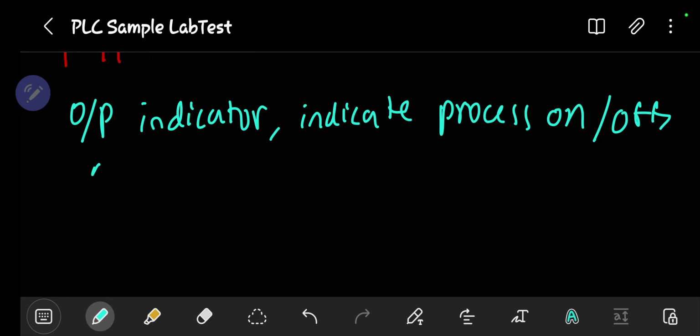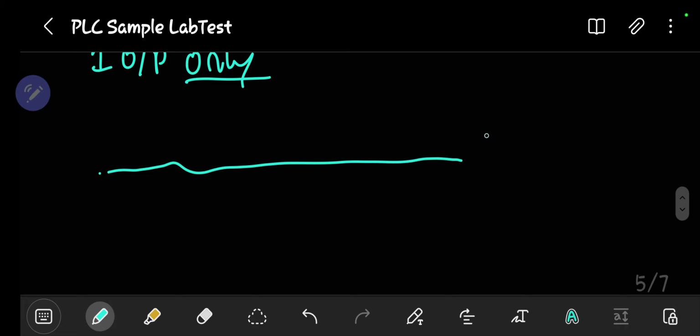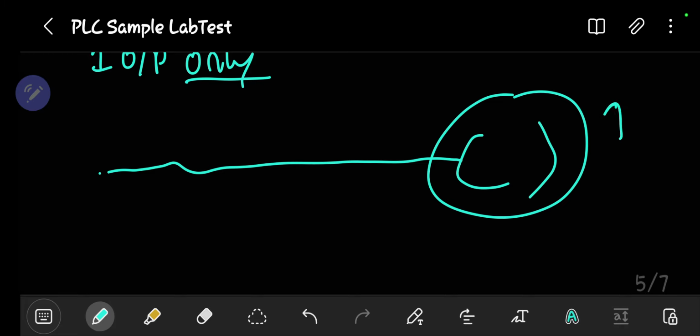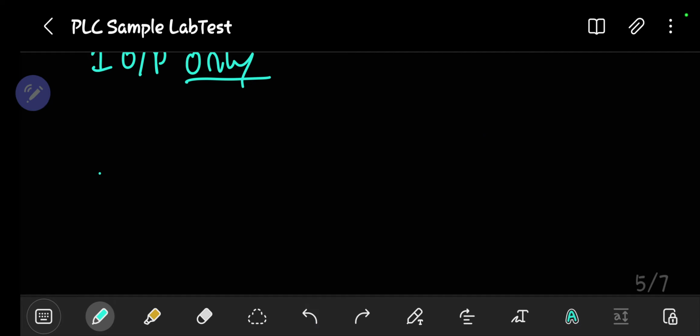So like I said, you can only have one output only, right? The moment you have two, it will conflict. Why? Because for instance, I say in step 3, one of my green LED is on, but then in step 4, my green LED is off. But then in step 3, I said that the green LED is to be on forever. So then what is the PLC supposed to do, right? If you want to implement this kind of conditions, we must do it onto only one output device. That means it'll be in like maybe one line, and then finally this is the output device, only one, right? Only one of it can exist. The moment you have two, your program's wrong, right?